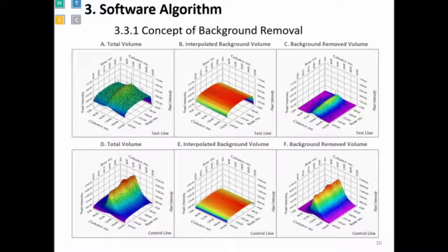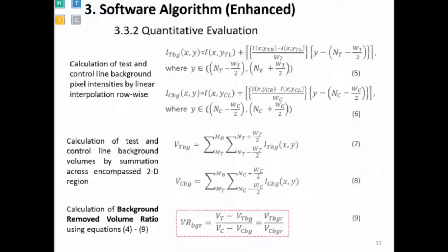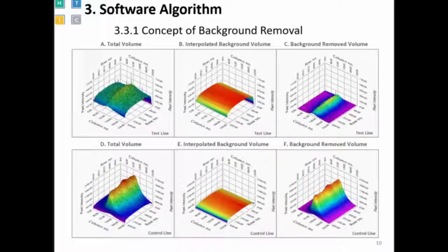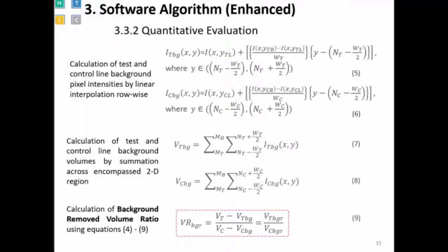You can see the test line with its baseline representing the background. We have no basic model for this, so we derive a model that performs linear interpolation to estimate and remove that background region. The background volume is subtracted from the actual test line volume, yielding the test line minus background — and the same process is applied for the control line. Equations show the initial intensity via linear interpolation, and the volumes of test background and control background are calculated accordingly. The updated VR background-removed equation becomes: V(test line minus background) divided by V(control line minus background).